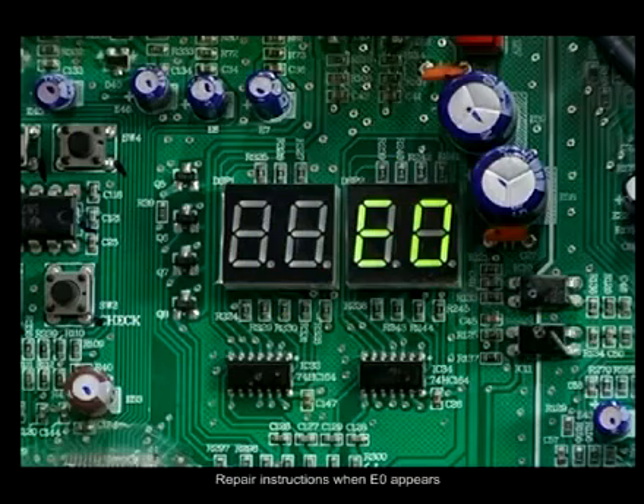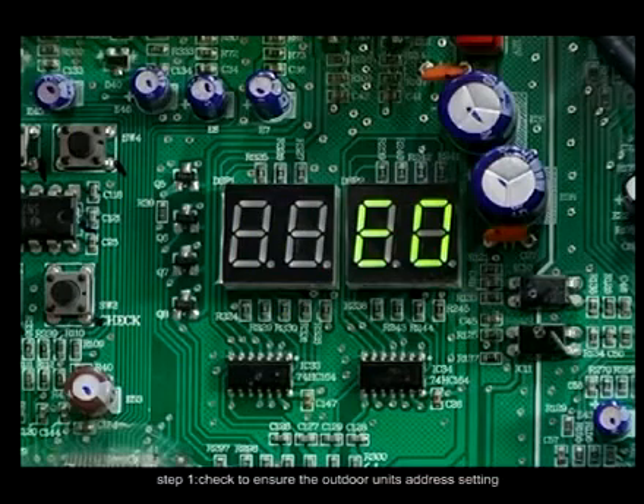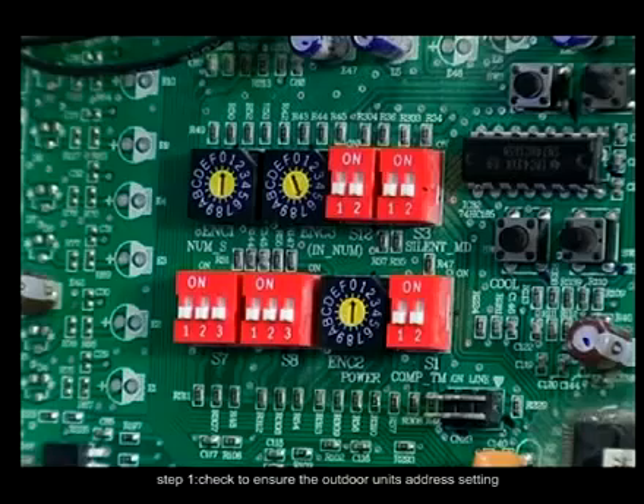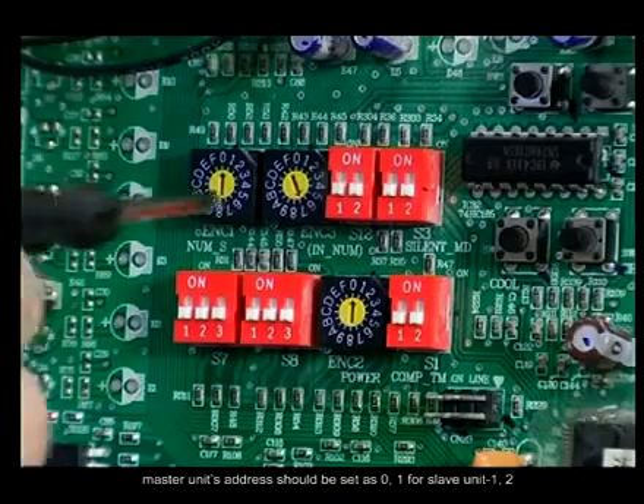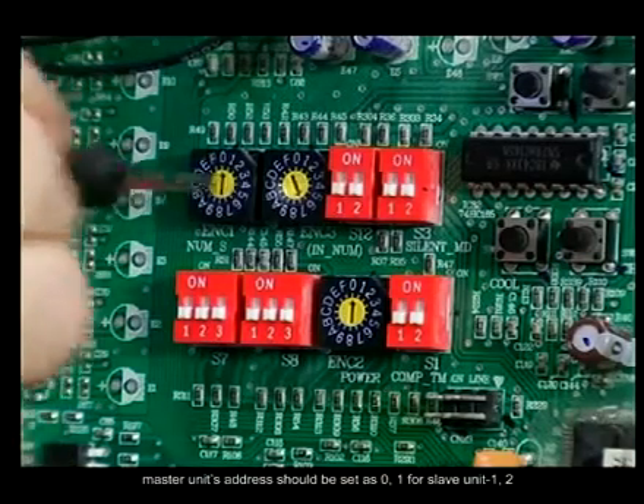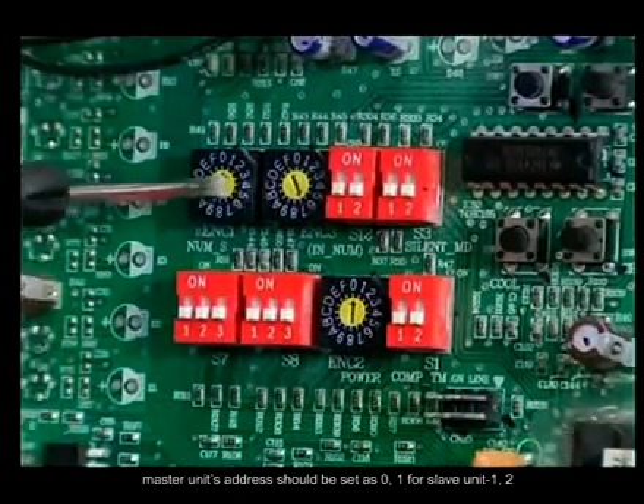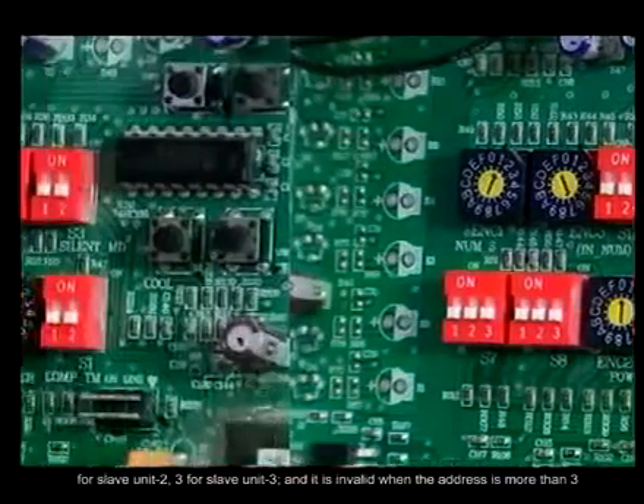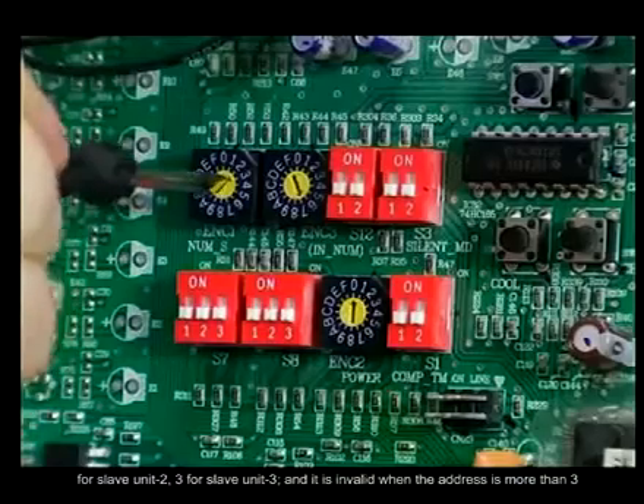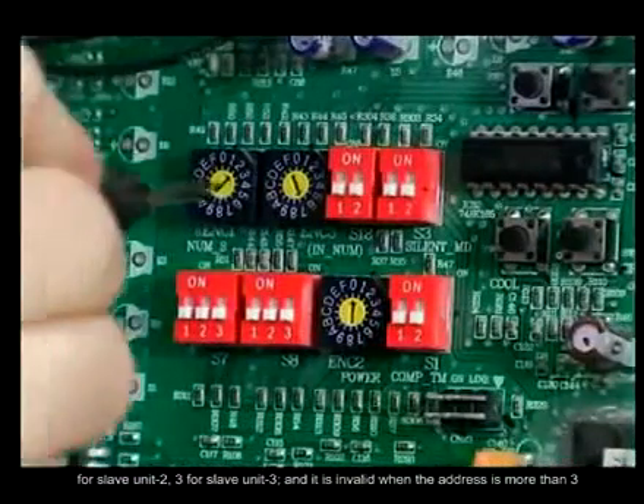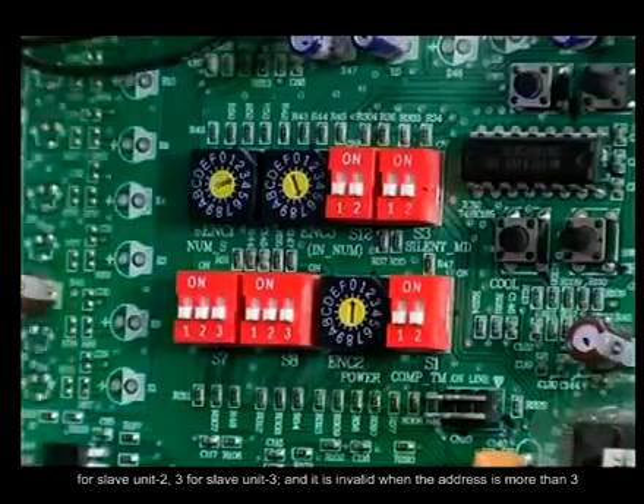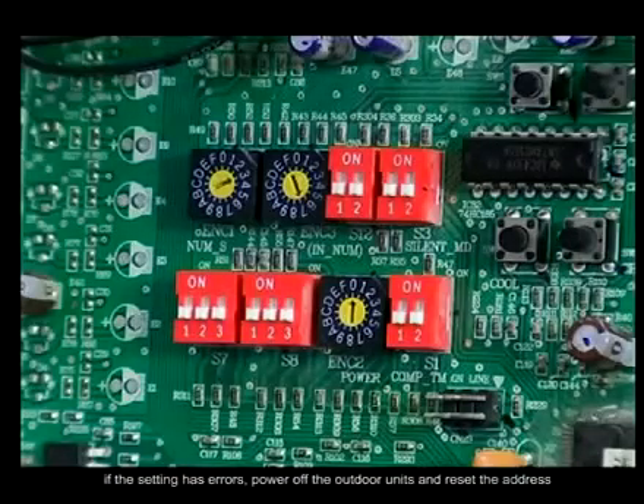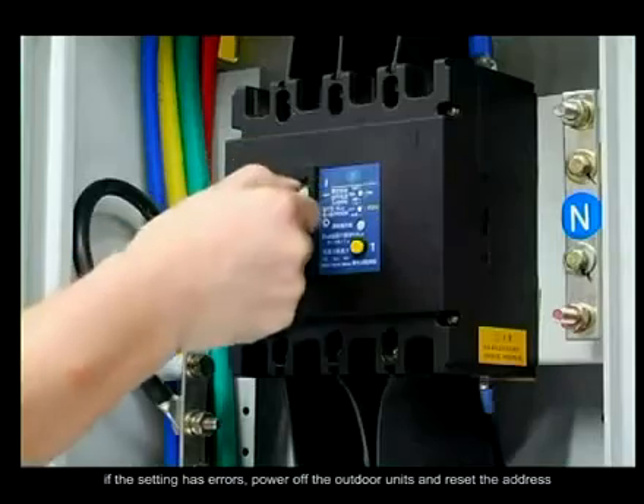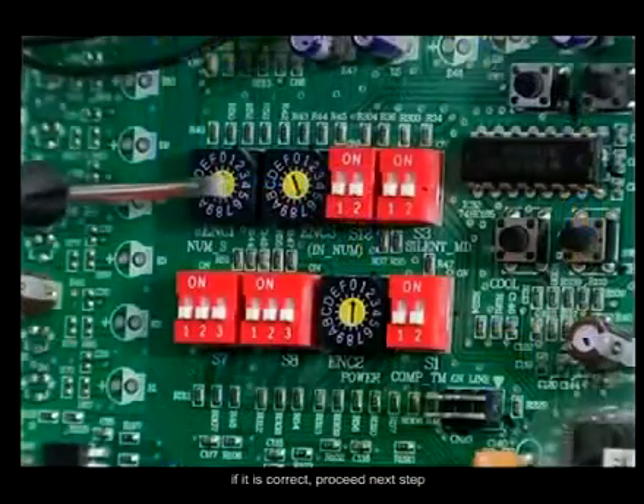Repair instructions when E0 appears. Step 1. Check to ensure the outdoor unit's address is set correctly. Master unit address should be set as 0, 1 for slave unit 1, 2 for slave unit 2, 3 for slave unit 3. And it is invalid when the address is more than 3. If the setting has errors, power off the outdoor units and reset the address. If it is correct, proceed to next step.